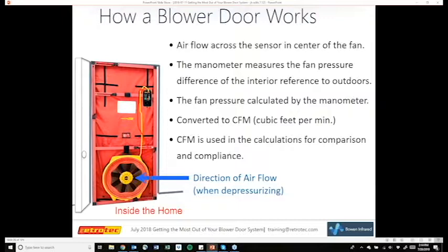Air flows across a sensor in the center of the fan, which is what this arrow is pointing to here. Your manometer then is able to read the pressure and calculate the flow. So as long as you have pressure and a known opening, which the manometer knows the opening of the fan, the manometer can then calculate the flow and convert it to CFM. And on this specific manometer, the DM32, you can enter the volume of the building that you're testing, and it can then give you ACH instantly as you're testing. That way you know you've passed or failed whatever target you're looking for.